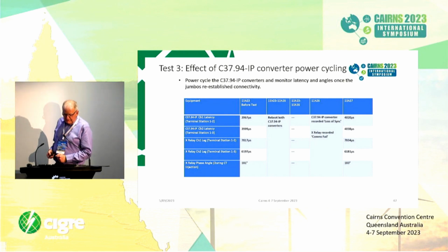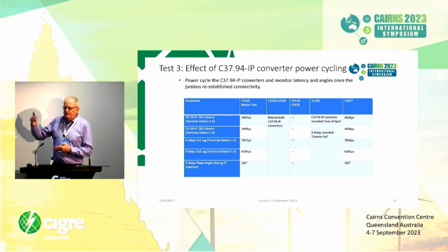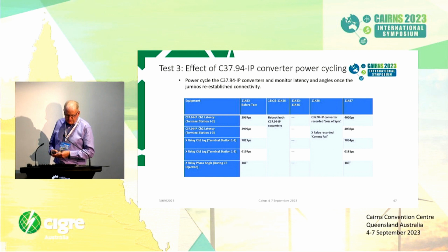So what we have done though in our system, we're a little bit nervous about the communication system flapping. If we were going to have some sort of intermittent communications fault in the system, we don't want the communications coming up and down rapidly. So we've introduced a script in our system which fails the communications for a period on loss of communications. But this test, once again, worked perfectly, really.